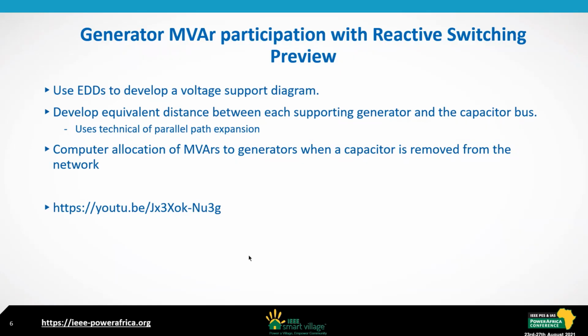Now, as part of this, you'll be seeing the use of a technique called parallel path expansion. Normally, we take multiple parallel impedances and we combine them into a single equivalent. In this case, to get an independent calculation, we actually take a single impedance and we break it into a number of parallel paths so that each generator has a separate parallel path directly from the generator to the bus with the capacitor or reactor.